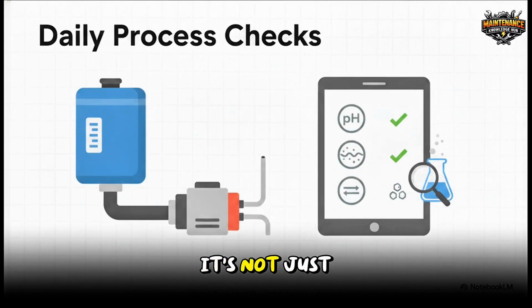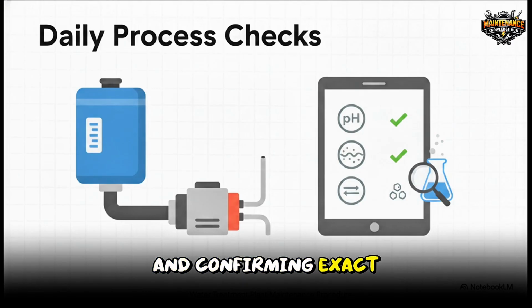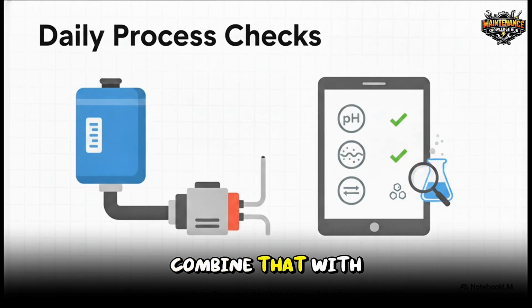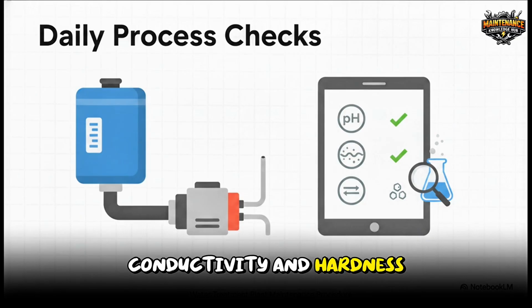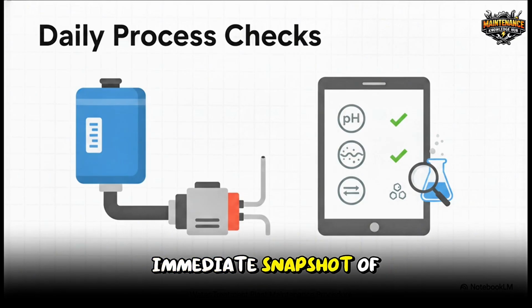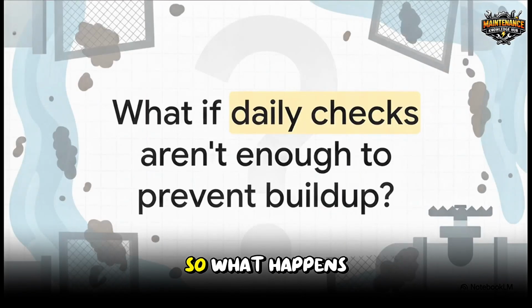But hey, it's not just turning wrenches. You and your team have to stay on top of the chemistry every single day. Verifying chemical tank levels, inspecting dosing pumps for any sign of a leak, and confirming exact injection rates means your chemistry is totally dialed in. Combine that with daily testing of pH, turbidity, conductivity, and hardness, and you've got a perfect, immediate snapshot of your plant's health. So, what happens when those daily visual and auditory checks just aren't enough?